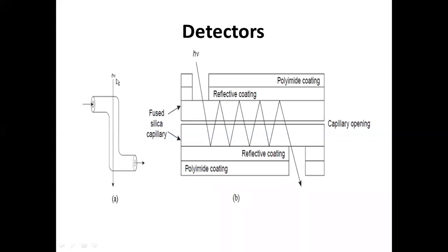Light radiation of known wavelength is passed through this particular cell, and by passing this, the amount of light energy absorbed can be calculated by using A is equal to 2 minus log T, because we are able to note down the transmission. This can be used to calculate the absorbed light energy manually. Otherwise, photomultiplier tubes or photodiode array detectors will do all this work.